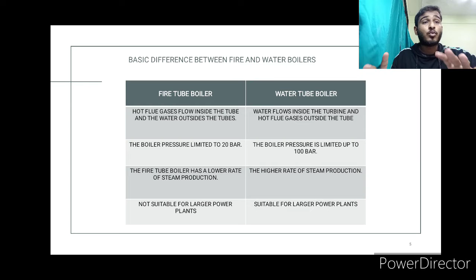We proceed to the next slide, where we are going to talk about the differences between fire tube and water tube boilers. The first difference is that in a fire tube boiler, hot flue gases flow inside the tube and the water is outside the tube, while in a water tube boiler, the water flows inside the tube and the hot flue gas is outside. The second difference is pressure. The boiler pressure in a fire tube is limited to 20 bars, while in a water tube it is up to 100 bars. The third difference is that the fire tube boiler produces a low rate of steam, while the water tube boiler produces a high rate of steam.